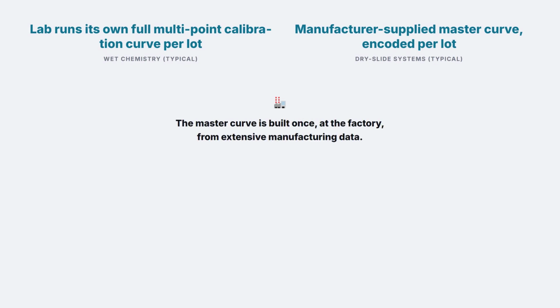This is where dry slide systems genuinely diverge from the multi-point calibration approach covered earlier for wet chemistry analyzers. Most dry slide platforms don't ask you to run a full multi-point calibration curve for every reagent lot at all. They use a manufacturer-supplied master curve instead, encoded directly into the slide lot's packaging or a barcode.